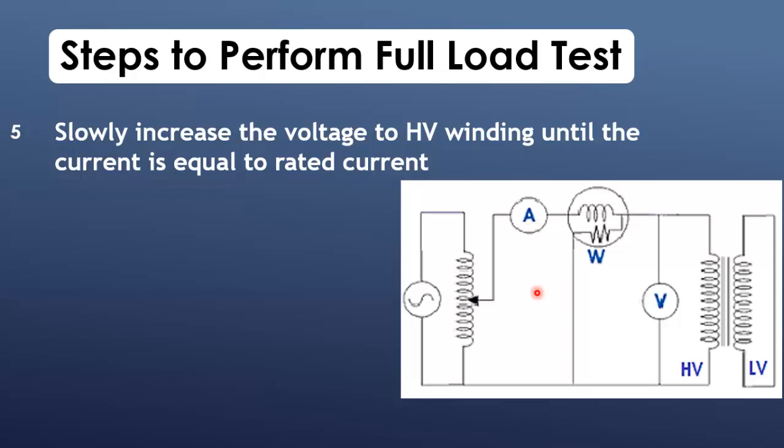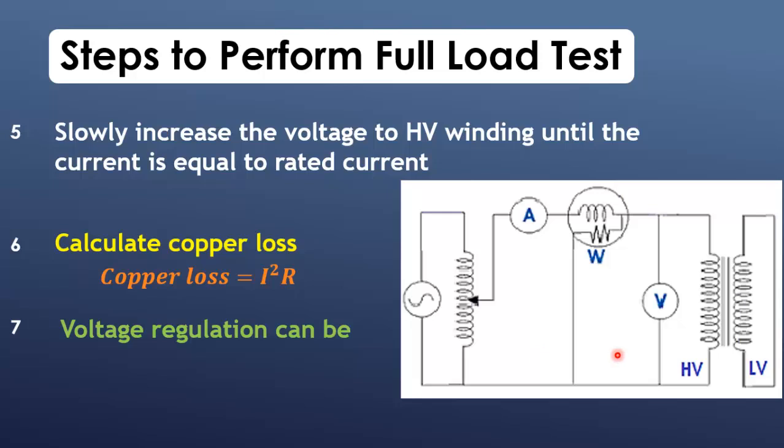The final step is to calculate copper loss, which refers to the power loss that occurs in the windings, both primary and secondary, of a transformer due to the resistance of the winding conductors when current flows through them, using the formula P equals I square R. Another purpose is to calculate voltage regulation by measuring voltage at no-load and voltage at full load.